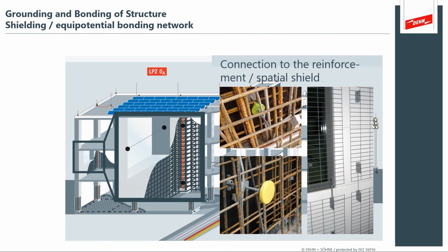This is really important in sites where you have high electromagnetic radiation, for instance, at a transmitter site or at a radar installation for air traffic control, for instance. What you would see in this environment is that the high intensity radiation fields will cause the electrical arcy sparky that you see. For instance, if you've ever thrown a piece of tinfoil into a microwave oven, you'll see that microwave radiation will light up and cause sparks to be induced into the metal foils. Well, that's the effect that you would see if you do not have a connected bonding system. So that's why you'll see a lot of emphasis on shielding and equipotential bonding networks.